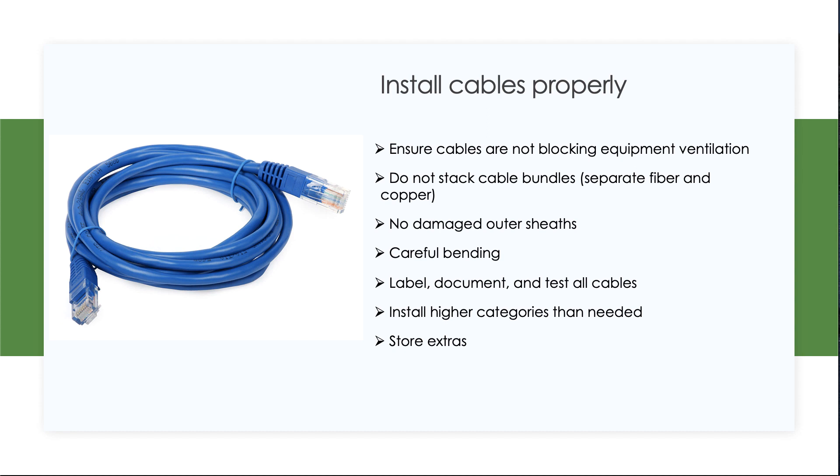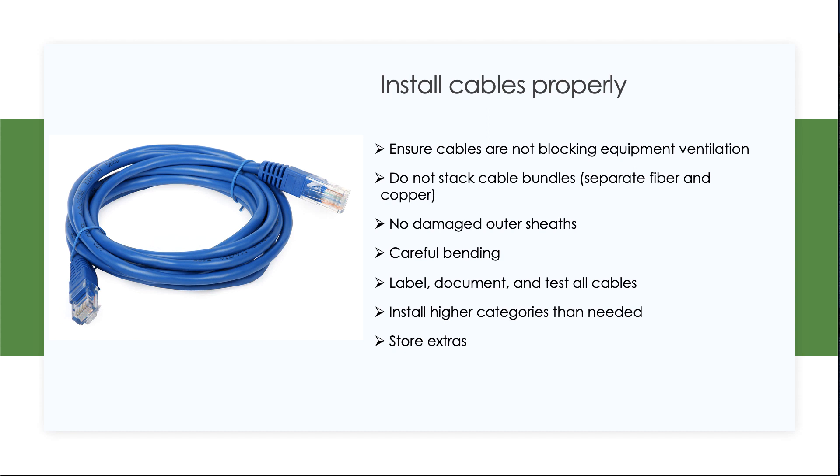Watch out for the sheathing on the outside of the cables. We don't ever want that to be damaged. With unshielded twisted pair copper, the second those twisted pairs inside get exposed, the efficiency of the cable and the chance for errors increases dramatically. Cables can bend, but make sure you know the limitations of the bending that a fiber or copper cable can do and don't push it. Try and do as little bending as possible, but make sure you're well within limits.